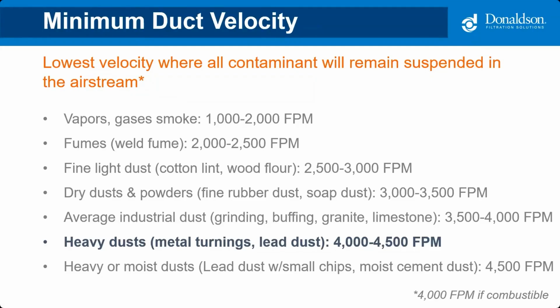If the duct velocity is too high, it'll require more energy to move the air through the duct. Ultimately, this could impact the size of the system fan, as well as create issues such as increased noise, abrasion, or wear and tear.